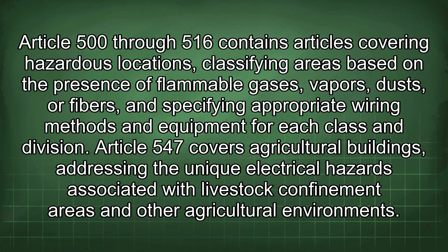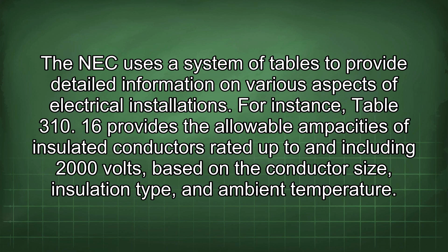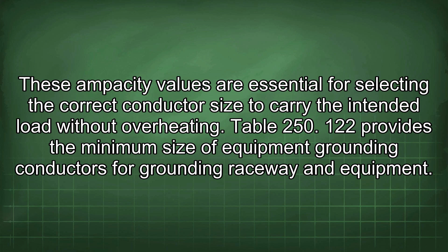For instance, Table 310.16 provides the allowable ampacities of insulated conductors rated up to and including 2000 volts, based on the conductor size, insulation type, and ambient temperature. These ampacity values are essential for selecting the correct conductor size to carry the intended load without overheating. Table 250.122 provides the minimum size of equipment grounding conductors for grounding raceway and equipment. This table ensures that equipment grounding conductors are sized appropriately to provide a low impedance path for fault current.